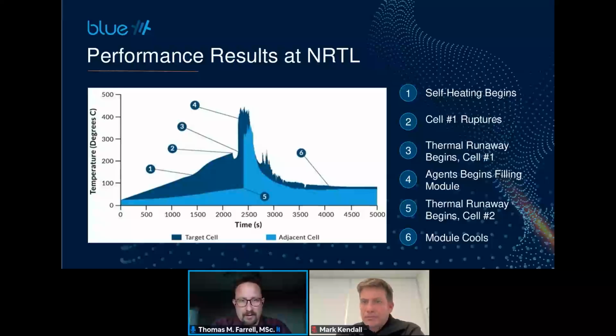Temperatures in other modules never got anywhere close to anything that could cause thermal runaway. So this is considered a pretty big win. The staff at CSA went back and looked at video, and while we don't instrument every single cell and every single battery, we can look at things at a higher level and think of it in terms of events. In that video, you see a chuff of smoke coming off. You consider that an event, and that might have been one cell. That might have been a collection of cells, but it was an event.